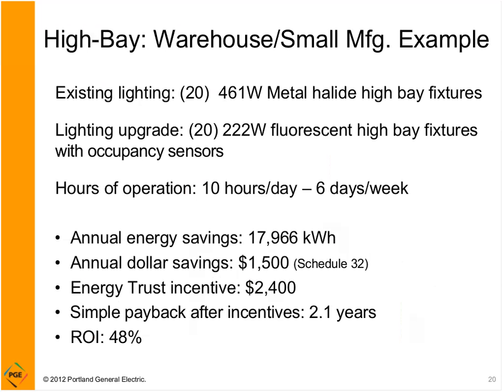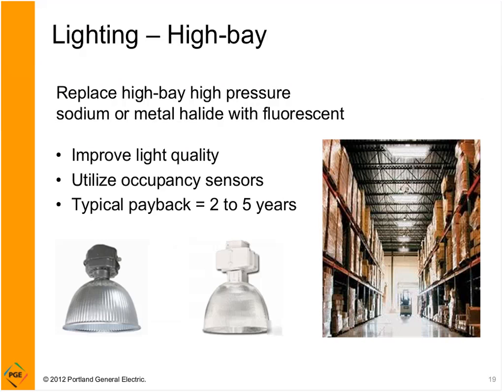And Garrett, what's the comparison of the light level before and after when you change them out? Does that change? It all depends on what you're looking for. You want to design the lighting so it meets the need of the space. If you have a light level that you are comfortable with, it would just be a matter of choosing a fluorescent high bay fixture that's going to have the equivalent light output. So it's just making the right choice for the light level that's needed in the space. One thing to note, there's lumen depreciation with the metal halide or high pressure sodium. The light level drops off pretty rapidly from the initial output with these types of fixtures. That's not really the case with fluorescent; it's pretty minimal. So that's another factor to consider as well.